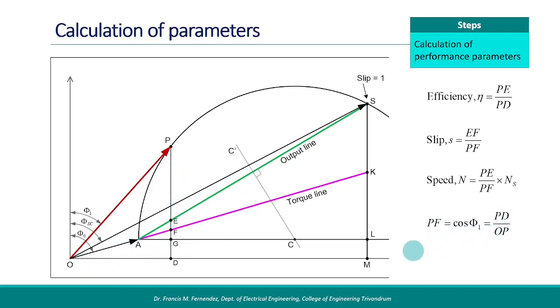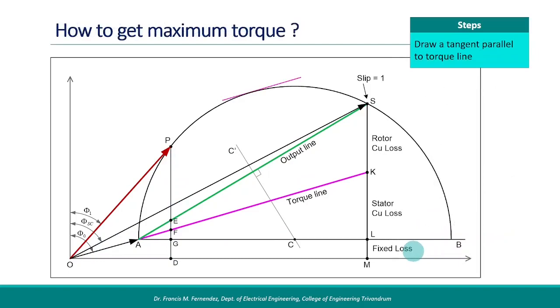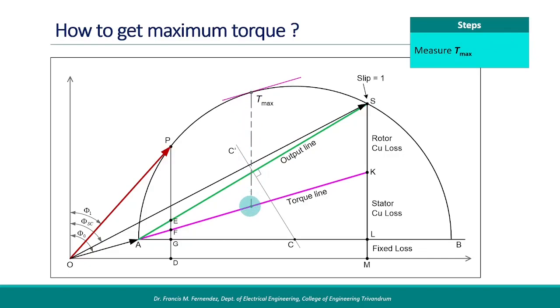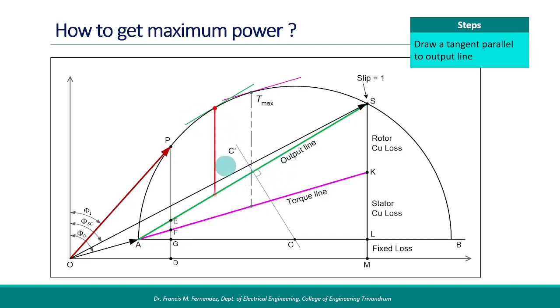Next, we shall see the procedure to find the maximum torque of the machine. Draw a tangent to the circle which is parallel to the torque line, then draw a vertical line from the point where the tangent touches the circle to the torque line. The length of this line represents the maximum torque in synchronous watts, using the selected power scale for conversion. To find maximum power output, draw a tangent to the circle parallel to the power line, then draw a vertical line up to the power line. The length of this line represents the maximum per-phase power output in watts.